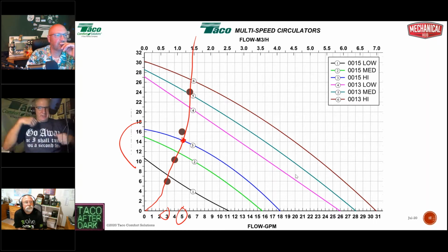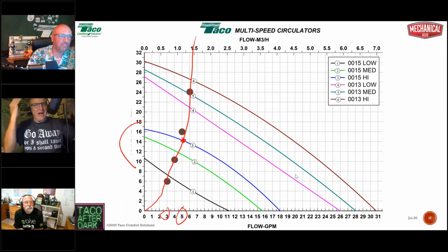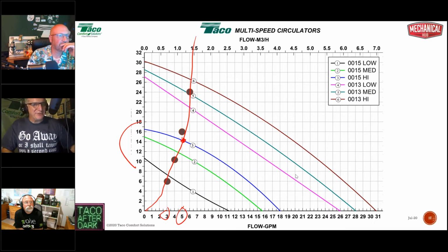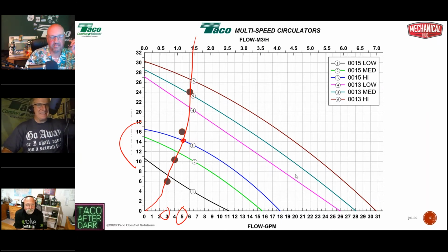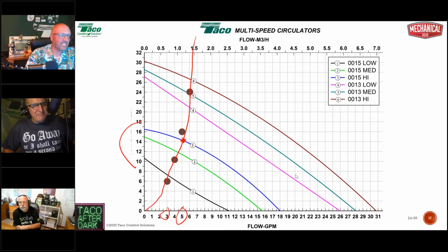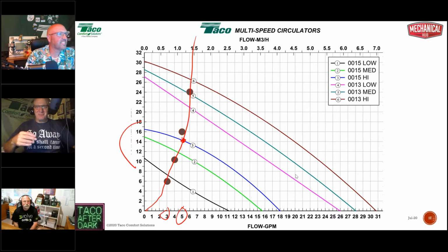I always use a 3-speed pump and a pressure differential bypass valve because that's the right way to do it. What happened is, illogically, it turned from a Band-Aid for a self-inflicted wound into, well, this is the right way to do a zone valve system. Whereas if you used a flat curve pump like a 007, which had been used for decades with zone valve jobs with zero noise issues, all of a sudden, because it only had 1 speed and not 3, people said, well, that thing's yesterday's news, man. Even though it was the right pump to use for that application. Yep. So that's kind of how pressure differential bypass valves became what the cool kids used for a while.